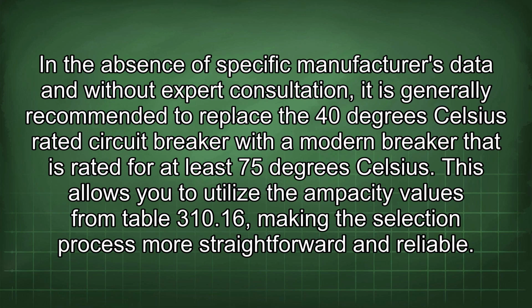In the absence of specific manufacturer's data and without expert consultation, it is generally recommended to replace the 40 degrees Celsius rated circuit breaker with a modern breaker that is rated for at least 75 degrees Celsius. This allows you to utilize the ampacity values from Table 310.16, making the selection process more straightforward and reliable.